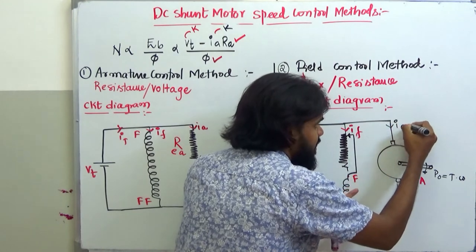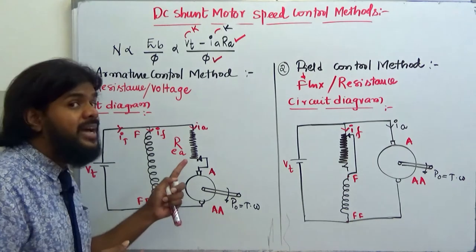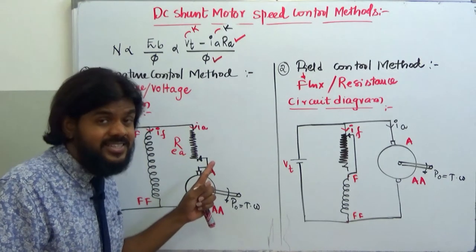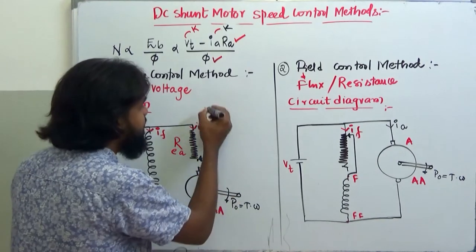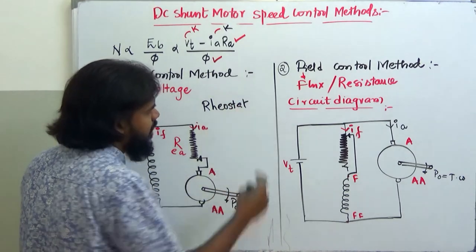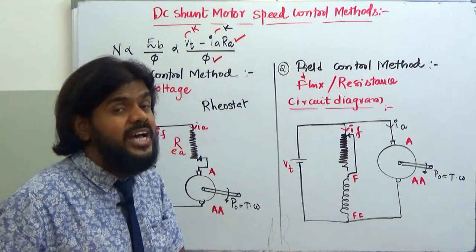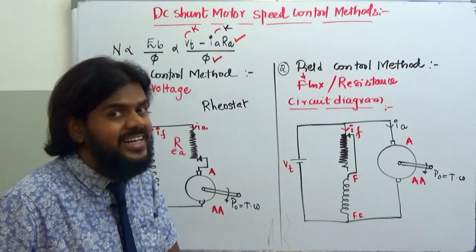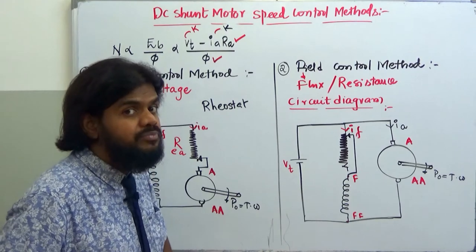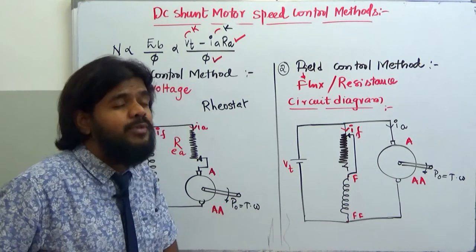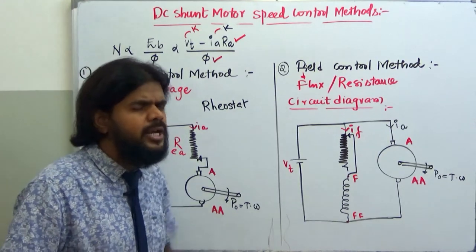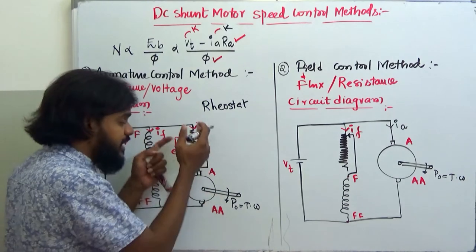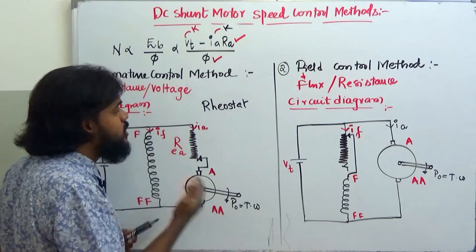In the armature resistance control method, since I cannot change the resistance of the armature winding itself, I connect an external resistor called a rheostat. A rheostat is a high current-rated resistor — its current carrying capacity is around 5 to 10 amperes depending on the motor rating.